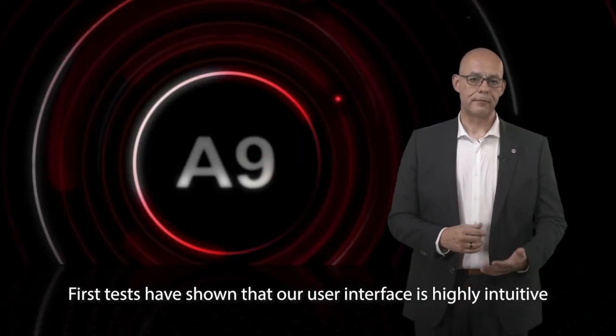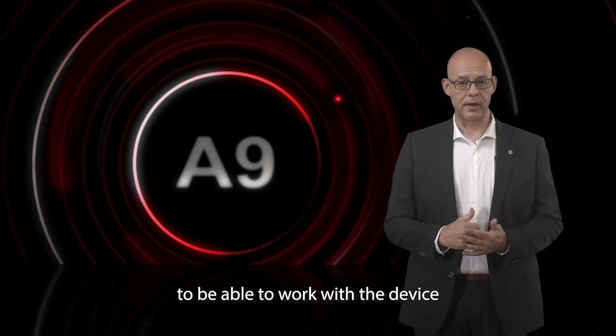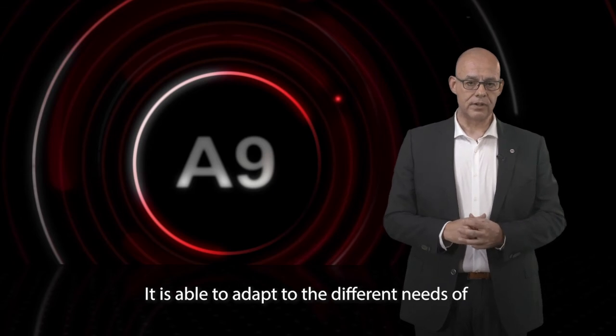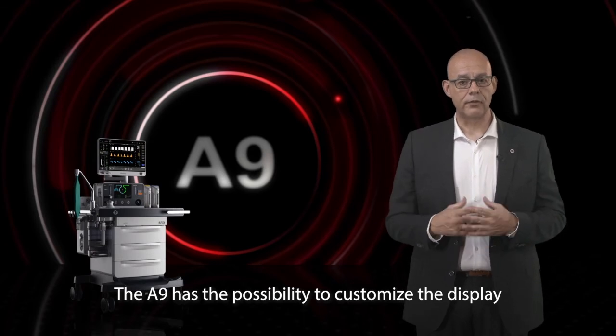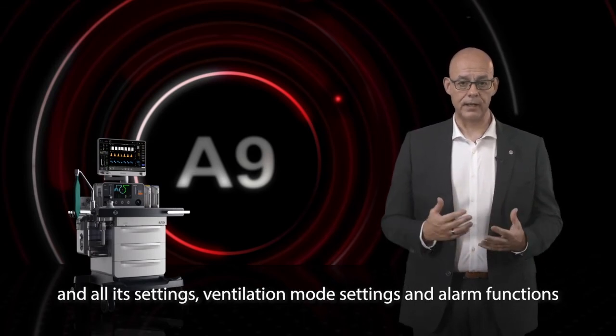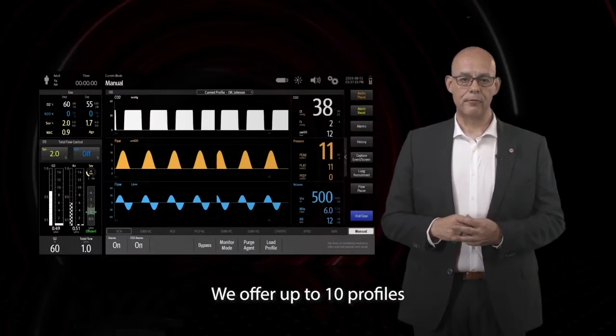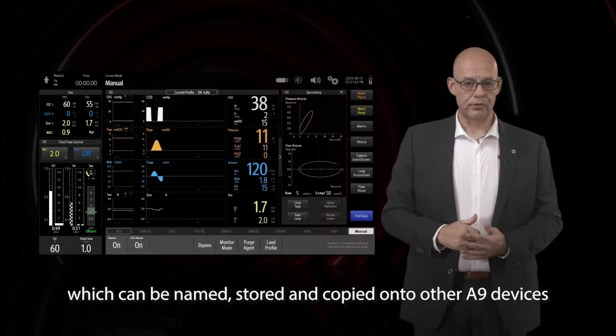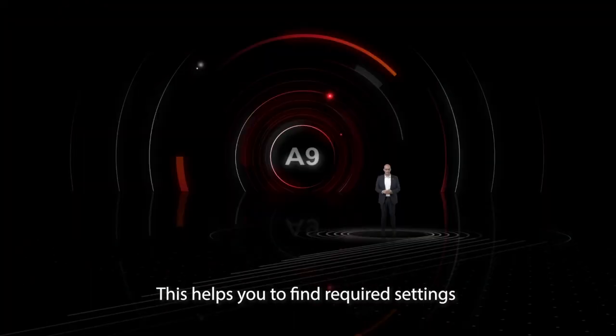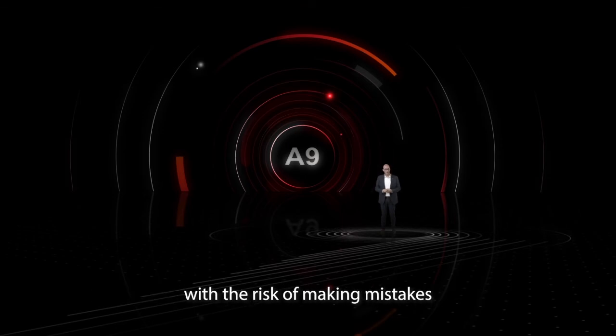First tests have shown that our user interface is highly intuitive — medical staff hardly needed any instructions to be able to work with the device. It is able to adapt to the different needs of anesthesia procedures and anesthesiologist preferences. The A9 has the possibility to customize the display, all its settings, ventilation mode settings, and alarm functions. We offer up to 10 profiles, which can be named, stored, and copied onto other A9 devices, helping you find required settings fast and safely without the risk of making mistakes.